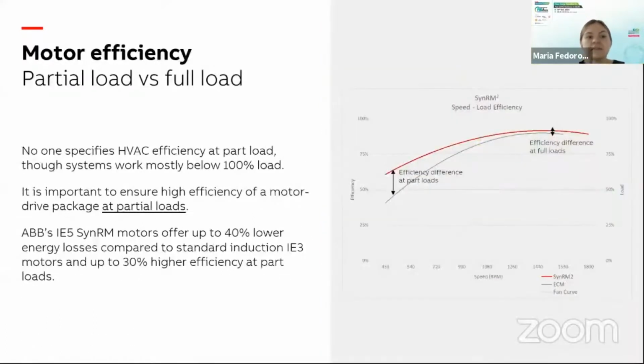Talking about motor efficiency, it's a must to use motors of a certain energy efficiency class to be compliant with local rules. But it's also good to understand that, for example, HVAC systems are not always run at 100% load, so it makes sense to look at the part load efficiencies of the motor technologies we utilize. On the right side of the slide, you can see how different motor technologies' efficiency varies with part loads and full loads.